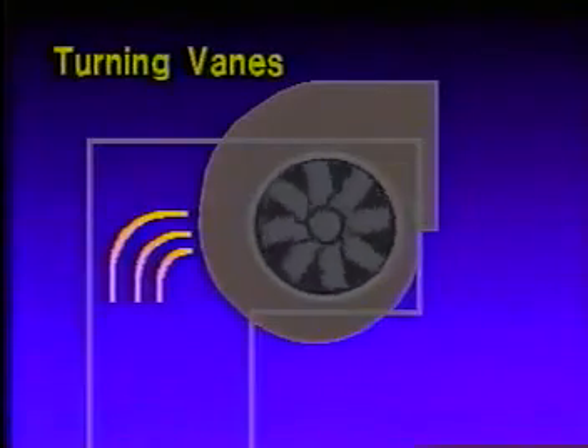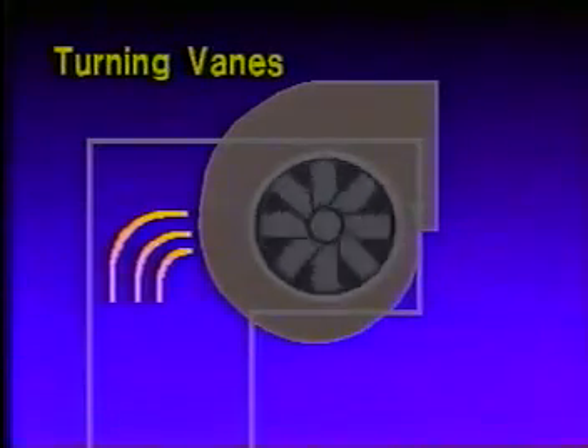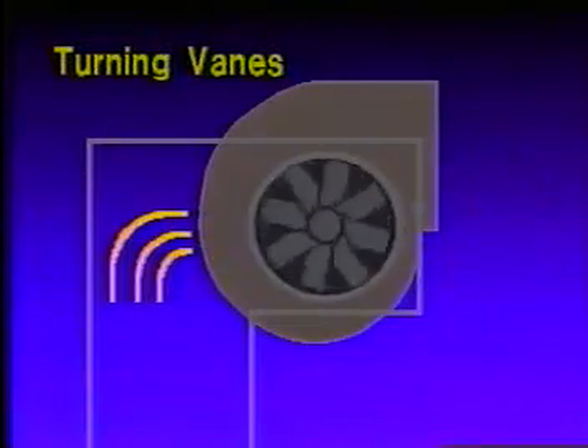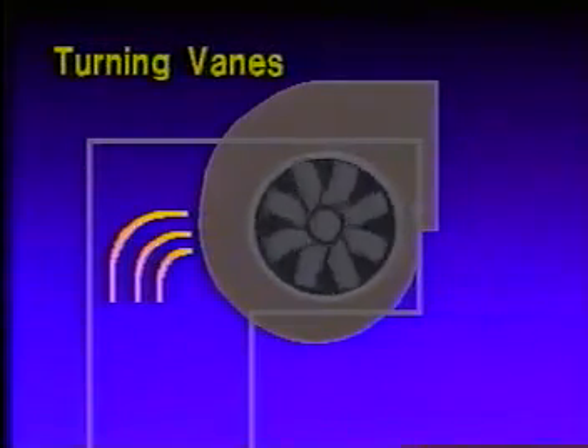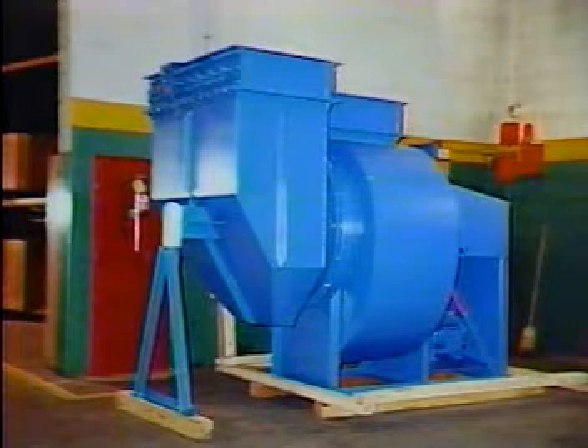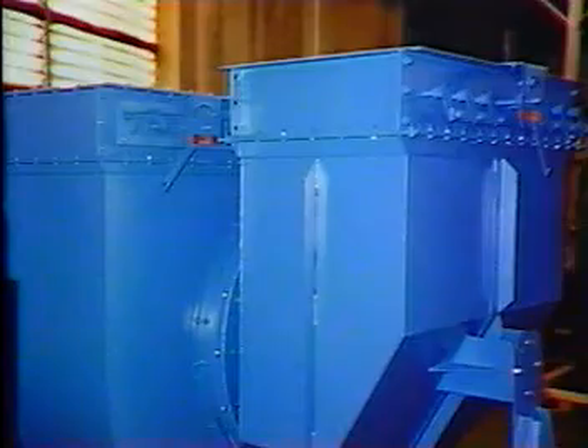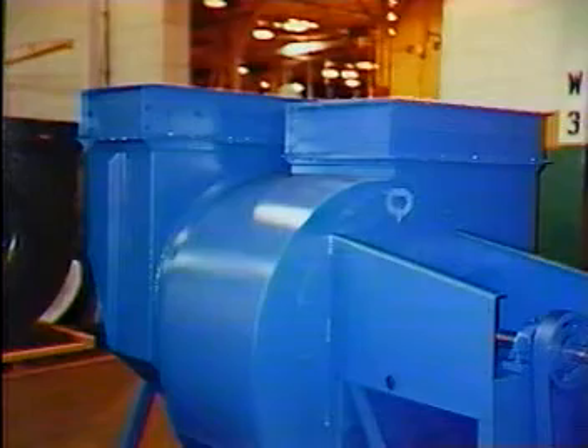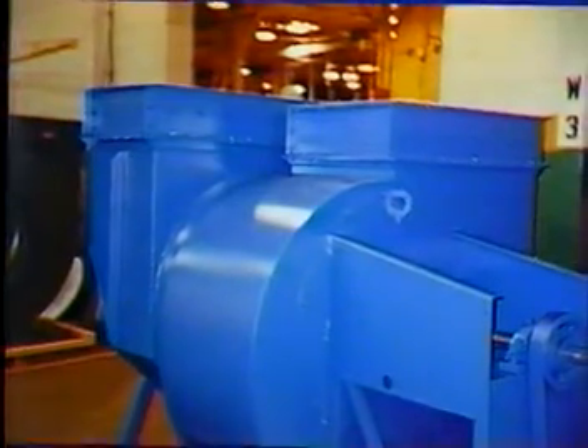Under extreme field conditions, you may need to install corrective devices and increase the fan speed to achieve the necessary levels of airflow. Your choice will always be to design the system, including the inlet ductwork, to avoid the expense of increasing the fan speed to compensate for system effects. Proper system design is the best way to maximize inlet efficiency.